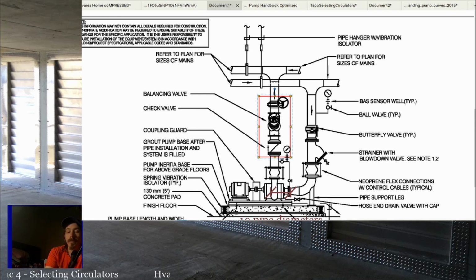But yeah, I've never dealt with it. Most of my pump experience, I don't have as much with dry coolers and stuff. Most of mine is boilers and chillers and cooling towers and things of that nature. I will tell you guys, we usually go through Baltimore Air Coil's design guide every year, at least as we talk about chillers. With cooling towers, you've got to be really cognizant of where you put those pumps and how you pipe them off the cooling tower, because you want to talk about a pump that can cavitate real fast. The pumps off the bottom of those cooling towers are usually pretty high volume and they're sucking the water straight out of the bottom of the pan, so they'll cavitate quicker than hell. But yeah, that's where most of my stuff is.